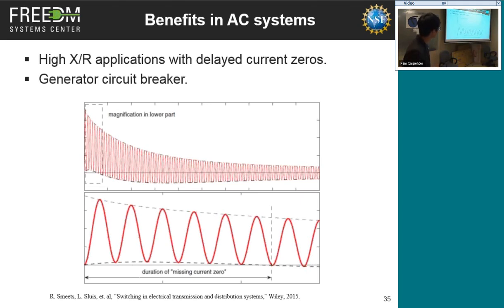We observe that for this period of time, there's no current zero. If you put an AC circuit breaker there, it does not work for this period. But if you use the hybrid circuit breaker, it works pretty well and very fast. It does not care whether there is a current zero or not, so it's a very good candidate for generator protection.